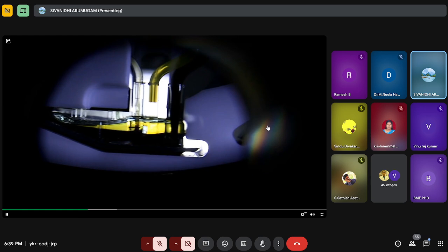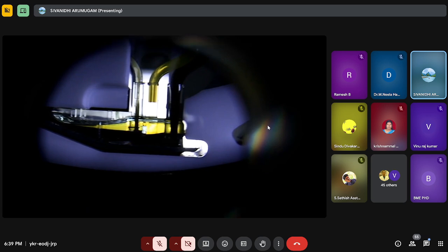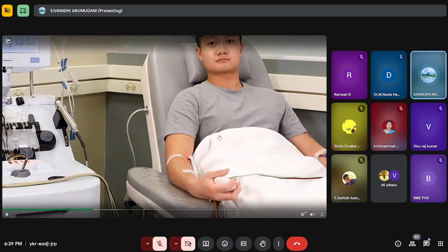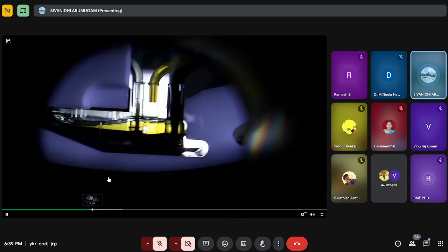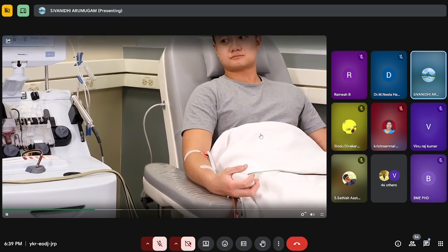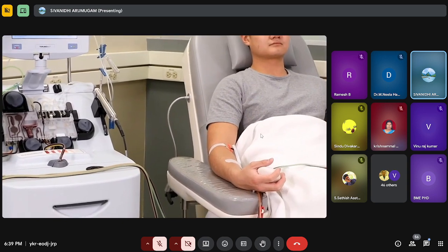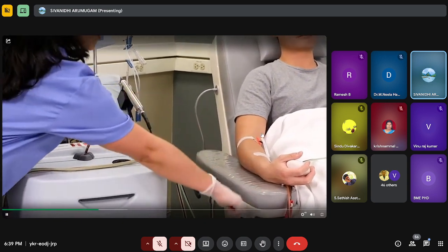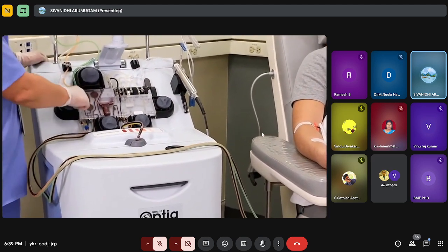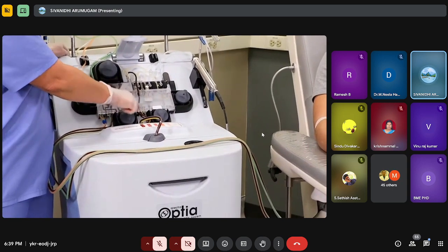In the channel, it begins to separate into three layers: red blood cells, buffy coat, and plasma. It is like a centrifuge that is rotating, but we are able to see the image properly. The red blood cells are continuously returned to the reservoir and pumped back to the patient. The collect pump pumps the buffy coat, which contains the target cells, from the channel and into the chamber.